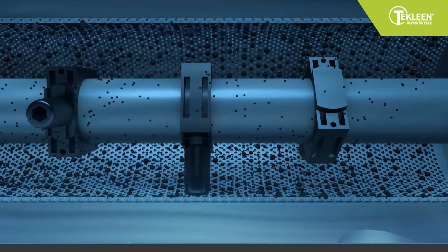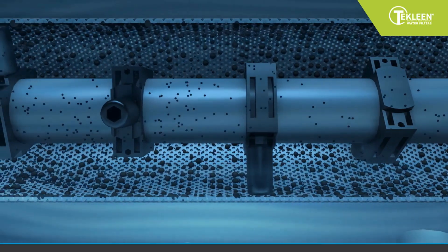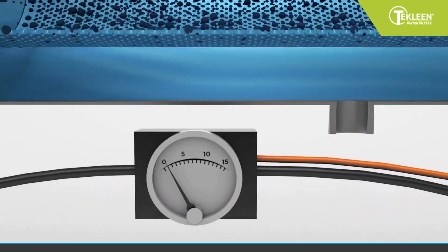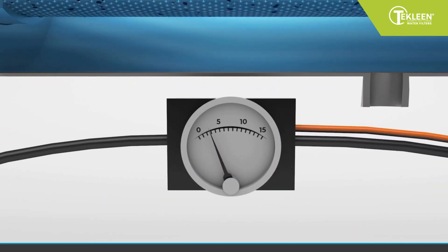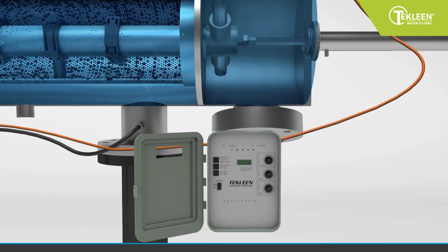This buildup of particulates causes a pressure drop at the outlet, which is constantly monitored by a differential pressure, also known as a DP sensor. Once a pressure differential of 5 to 7 pounds is reached, the electronic controller activates a flush valve to initiate a backwash cycle.